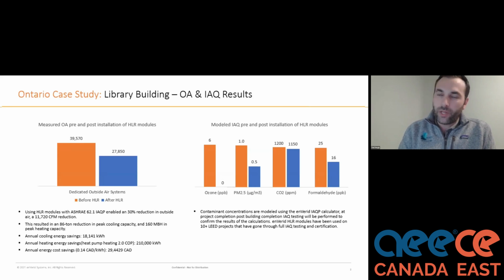Then we also just modeled out from that calculation what the levels of the contaminants of concern in that space will be. If you look at formaldehyde, 33 micrograms per meter cubed is the limit. 33 parts per billion is the limit in terms of applications for ASHRAE buildings. We're half of that in this application here.